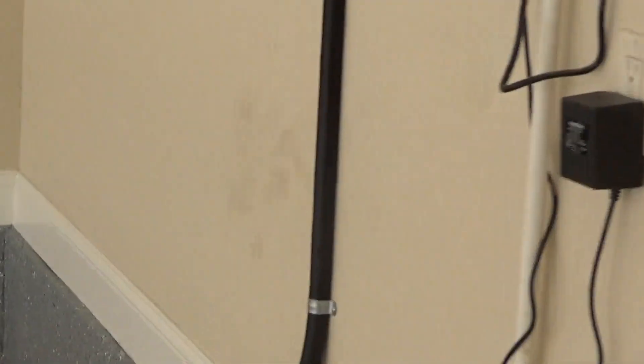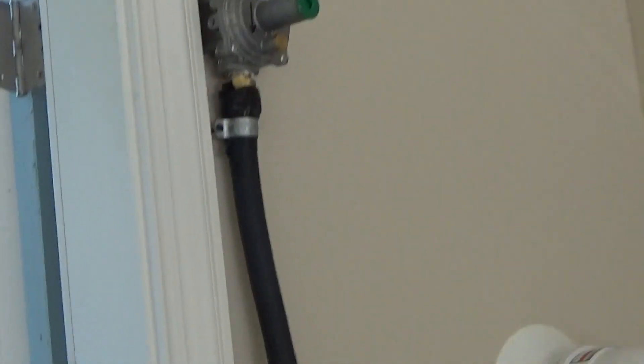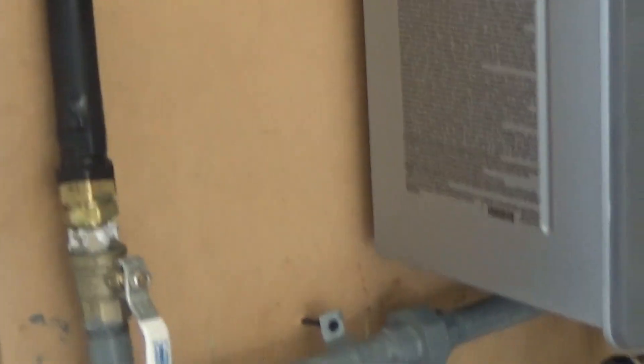Basically, we have two-pound gas systems, and I'm going to go outside and show you the gas meter. What we did is we came off of the two-pound side of the meter and ran a dedicated gas line directly to the unit. We came in and ran three-quarter CSST gas pipe above the door and then came down into the unit.